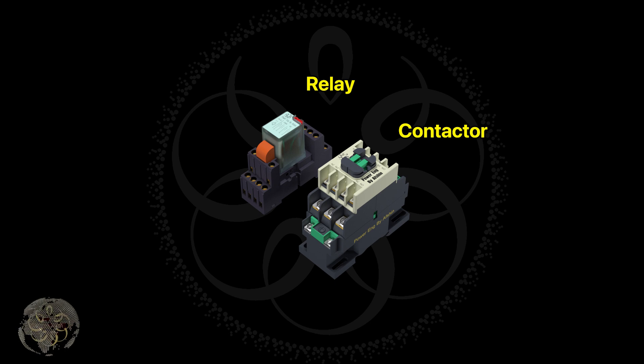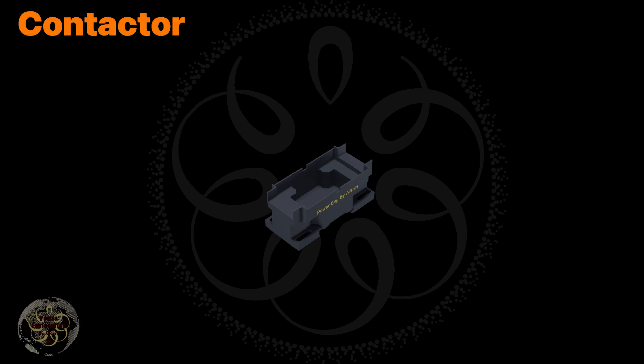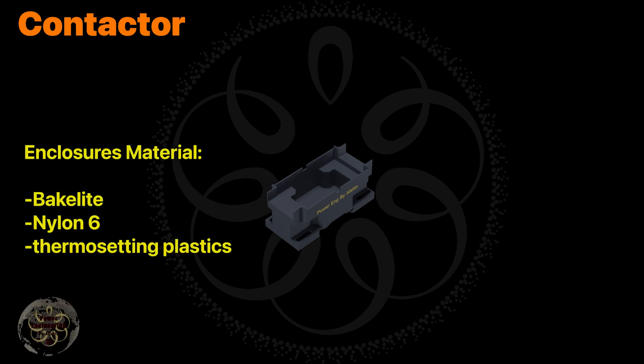Now let's take a closer look at the internal structure of a contactor. Here you can see part of the contactor's enclosure. The enclosure is a frame that houses the contacts and the electromagnet. Enclosures are made of insulating materials like bakelite, nylon 6, and thermosetting plastics to protect and insulate the contacts while also providing safety from accidental contact.